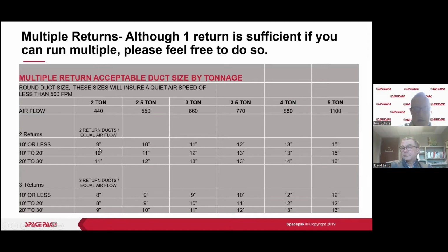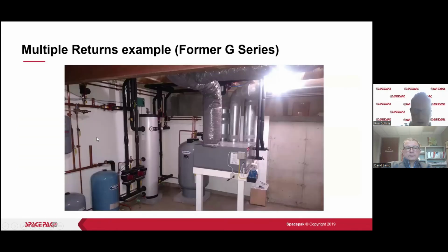It's going to be hard to find a 9-inch flex. This is the only place, by the way, the return, where we're going to use flex on our system. We don't use flex collars. We want a rigid duct installation on the plenum side. But on the return side, we could use flex duct. We just have to use the right size flex duct. So here on a 2.5 ton, if we had one that was 10 foot, here we go, that's 10 inch we could use on that. And if we had a 15 footer, it comes out to 11 inch. We'd probably up that to 12 inch. All we're doing here is making up for the extra length and the extra pressure drop that we'll get from that length. Okay, so not too hard to understand.